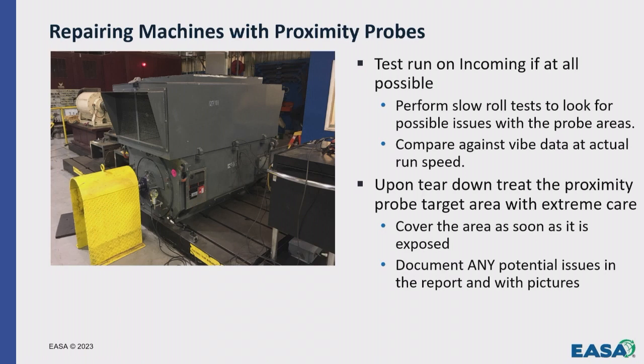So just bump it, get it up on the fluid film, and see what your vibration levels are at that speed. If at that speed you're seeing high vibration levels, that's a good indication that you've got some electrical runout, something's going on with that machine, and you need to present that to the customer now. Because as you know, if you don't present it on the front end, then on the back end, if you fail the acceptance testing, it makes for a pretty difficult conversation.